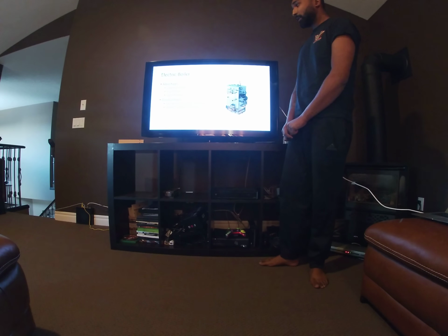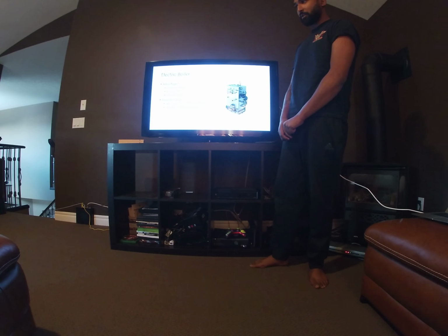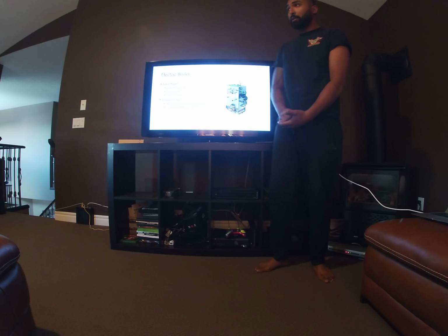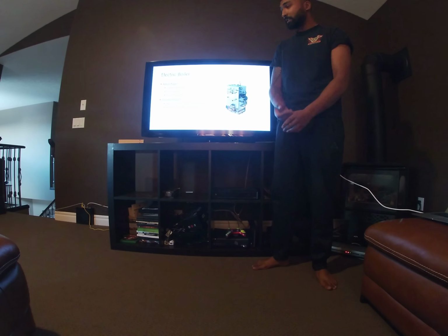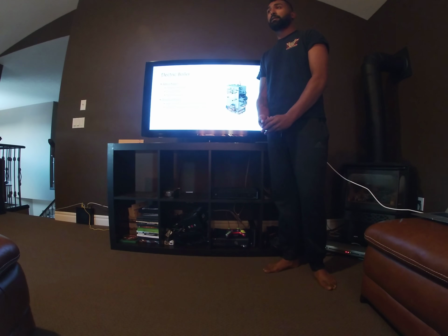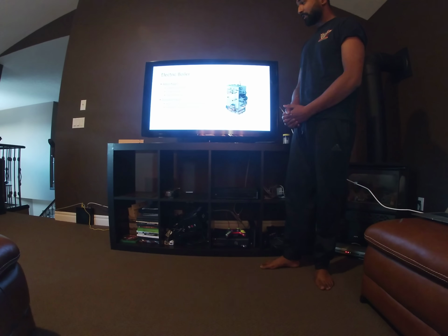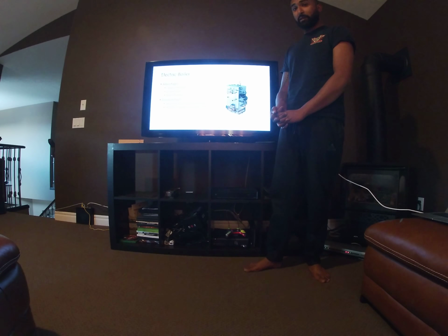Next will be the electric boiler. They require no fuel, so it's just electrodes submerged in water, and the electricity the building or city provides will boil that water. There's no pollution because there's no fuel to burn. It needs no stack because there's nothing it burns. It has a 98% efficiency rate, so there is really no heat waste. Everything is mostly used.